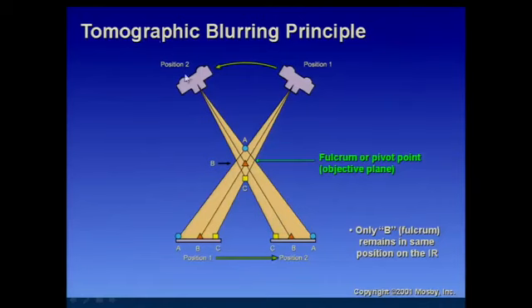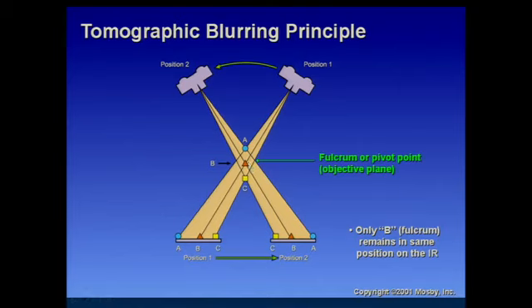People started to work on ways to minimize that effect. This picture should look familiar, because I showed you something like this when we talked about tomosynthesis. The more things change, the more they stay the same—we were doing conventional tomography going back 80 years ago. Basically, we rotated the x-ray tube and the film in concert with each other, and what you got was a single plane in better focus with planes above and below out of focus. Unlike today's digital technology, if I wanted a different depth of plane, I had to repeat the process using a slightly different fulcrum point.